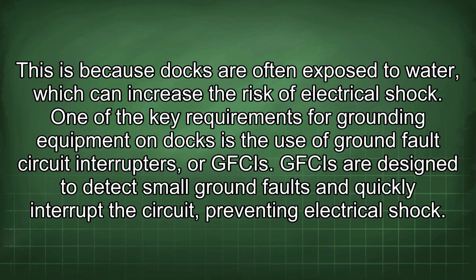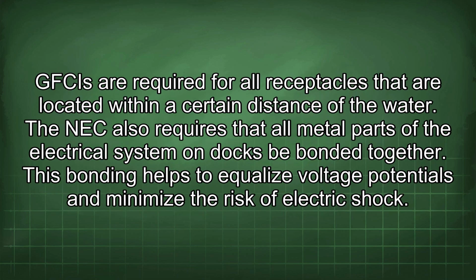One of the key requirements for grounding equipment on docks is the use of ground fault circuit interrupters, or GFCIs. GFCIs are designed to detect small ground faults and quickly interrupt the circuit, preventing electrical shock. GFCIs are required for all receptacles that are located within a certain distance of the water.